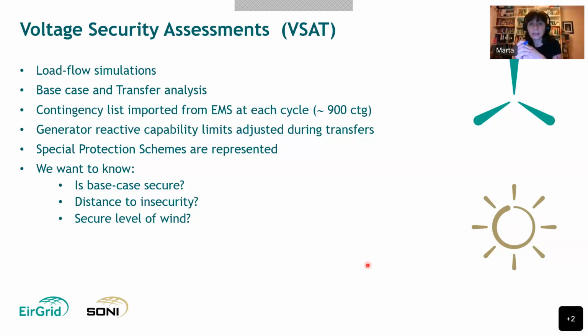One transfer is maximizing the amount of wind that we can incorporate into the system. So we scale the wind up and scale down the conventional generation. We run that series of simulations and identify the limit, the maximum limit of wind. This tool also uses the contingency list imported from EMS, where grid controllers can enable or disable certain contingencies depending on operating conditions at the time. Normally this is about 900 contingencies that we run in VSAT.